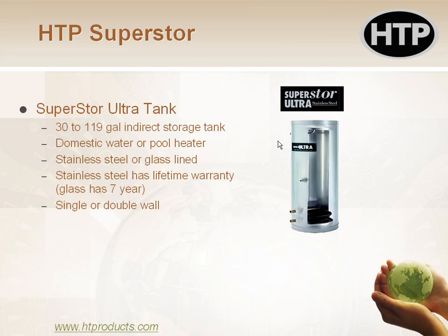Along with those boilers, if you're going to do domestic water, you need to have an indirect water heater, which, like I said before, is basically a water heater tank, but instead of a gas burner on the bottom, it has a hot water coil. And then obviously there's no venting for flue gases because the venting happens at the boiler, not at the tank. You can get these in stainless steel or glass lined. At our office, we stock them in stainless steel because they have a lifetime warranty that way. If you get a glass one, it has a 7-year warranty, just like a regular water heater might. And you can get them in single or double wall, depending on what the code requirements are of the area that you're in. Different municipalities have different rules on that.